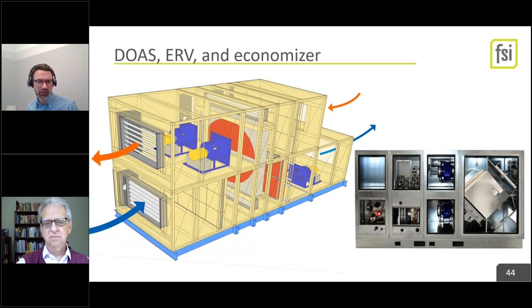On an energy recovery version with humidity weighed in, it's got like error bars to it, kind of. So we only get to heat to 55. We'll want to keep energy recovery all the way up, but we only get to cool to, is it 80? I'd have to go look that up. So we would be using free cooling to 72 maybe, and below 62, you're probably going to keep using the energy recovery. You don't want too cold air moving into a space. The likelihood that it's 62 out and you're really ramped up and cooling, you'd need a huge solar load or huge people load.